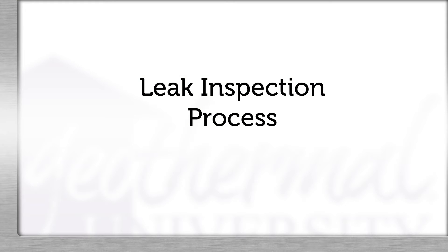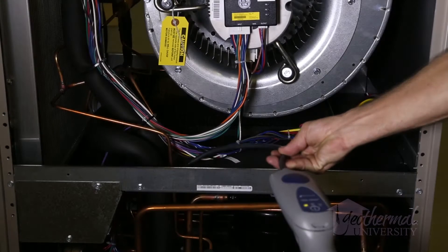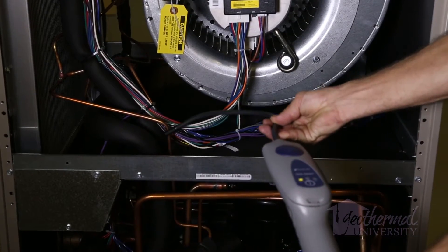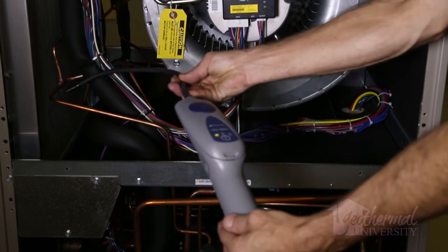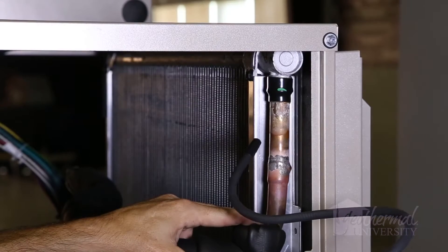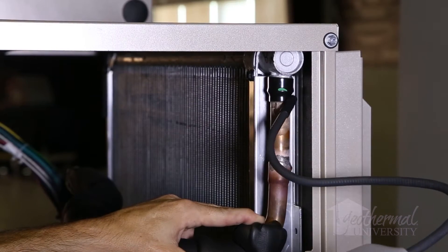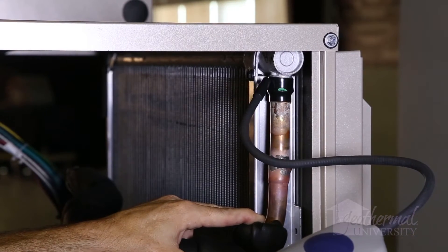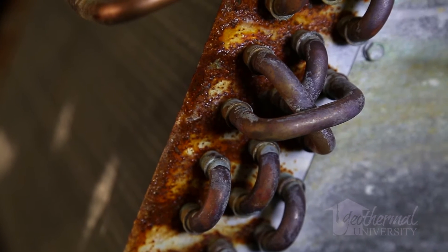If you suspect the refrigerant system has a leak, it is important to have a good leak inspection process. In a newer system, the most logical place to look for a leak is a braze joint, mechanical connection, or transition joint. As the system ages, you may begin to check the component's degradation due to corrosion.